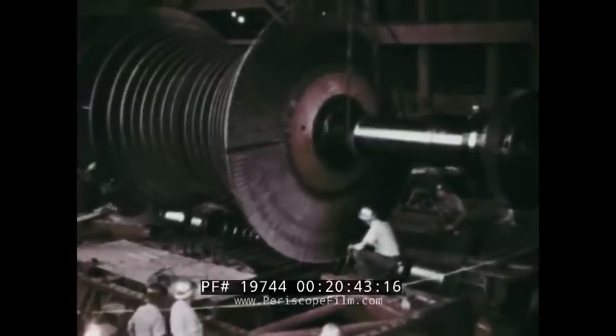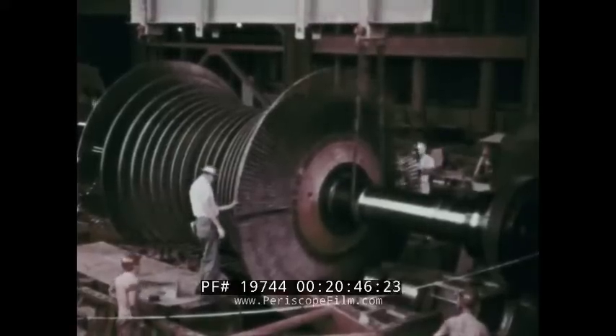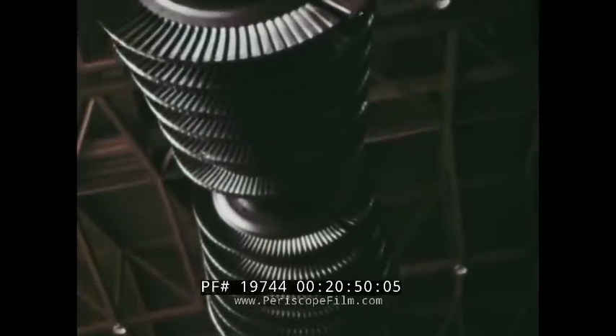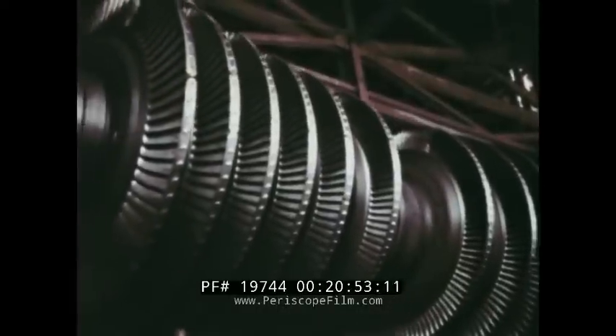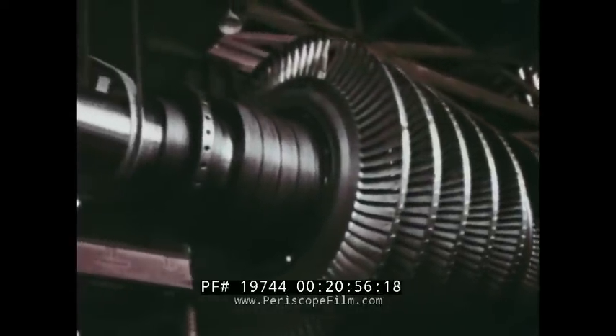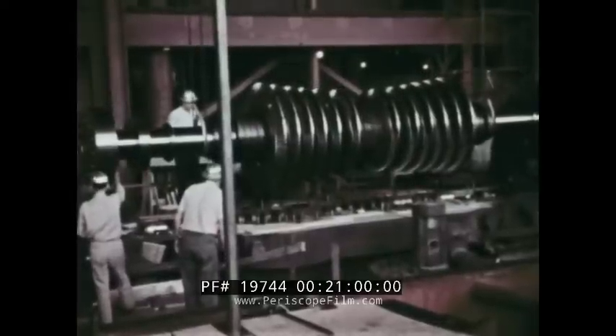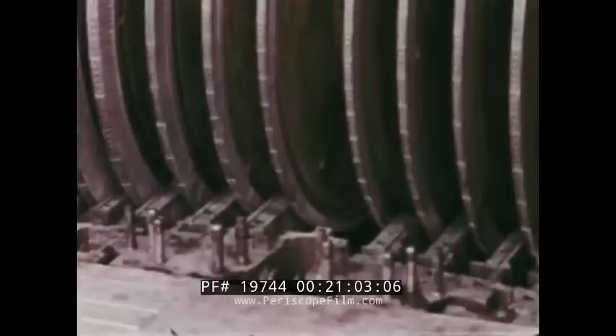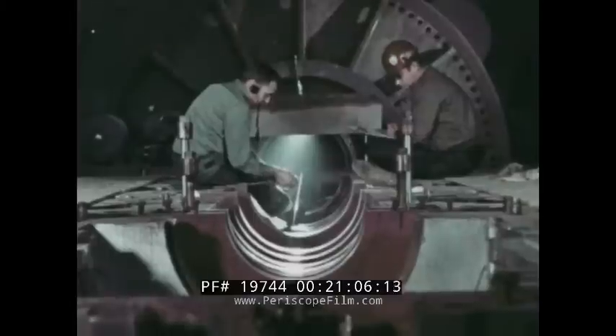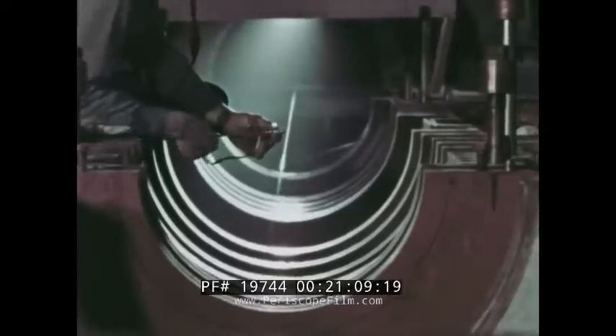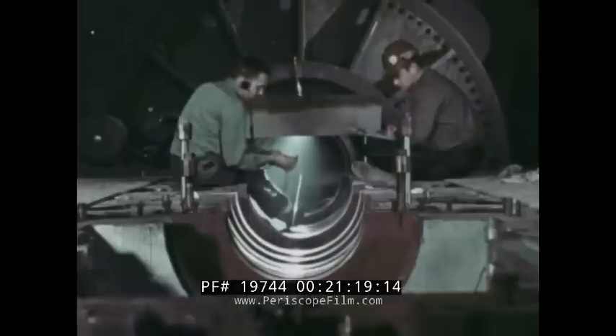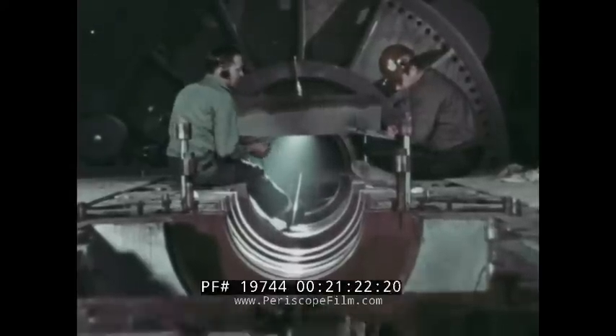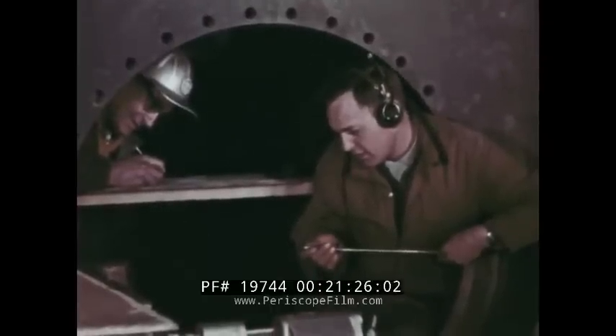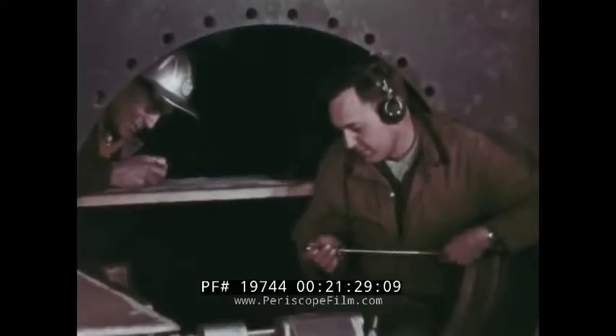The low-pressure rotor turns at the rate of 1,800 revolutions per minute. The high-pressure rotor at 3,600. The speed at the tips of the low-pressure turbine blades is close to the speed of sound. The space between those blade tips and the surrounding casing is less than 1/16th of an inch. Under these conditions, the alignment of the rotors was one of the most intricate tasks of construction. Stationary turbine parts were lined up to a piano wire stretched on the theoretical center line. Even the minute sag in the wire was accounted for. The accuracy of alignment had to be within 1/20th of the thickness of a sheet of paper.